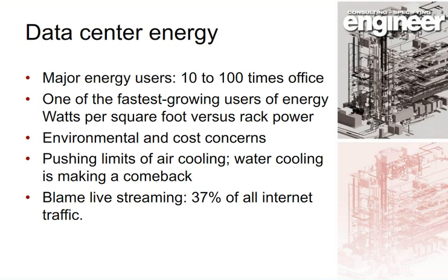In the past we've used watts per square foot as a metric for how much energy data centers use — it was not unusual to hear 100 watts per square foot. But kilowatts per rack is now the most common energy metric, with upwards of 30 to 50 kilowatts per rack not uncommon. With all this energy use, cooling is also becoming challenging. Water cooling is making a comeback, and with the growth in cell phones and live streaming videos, we're seeing a great increase in internet traffic during peak times.